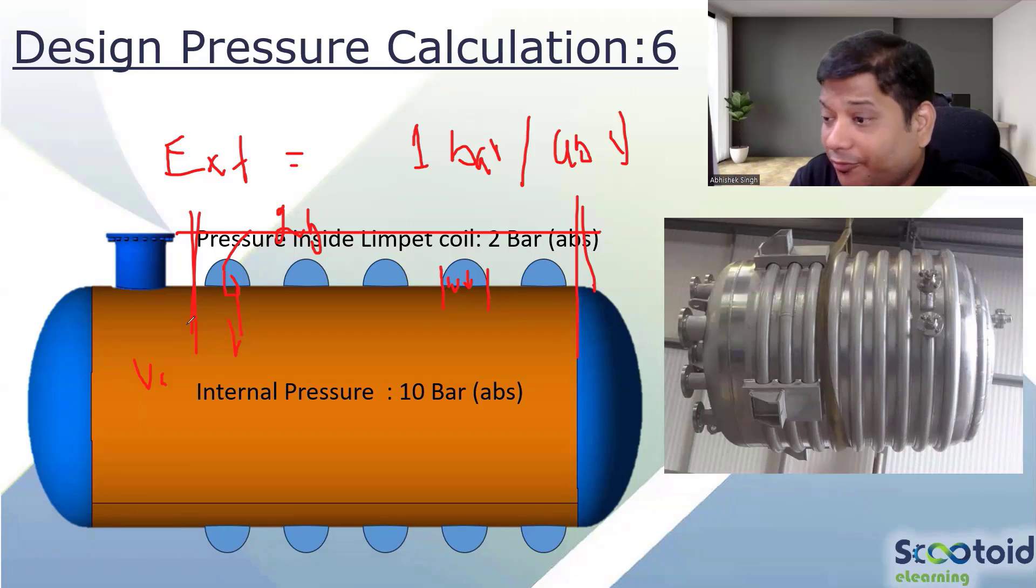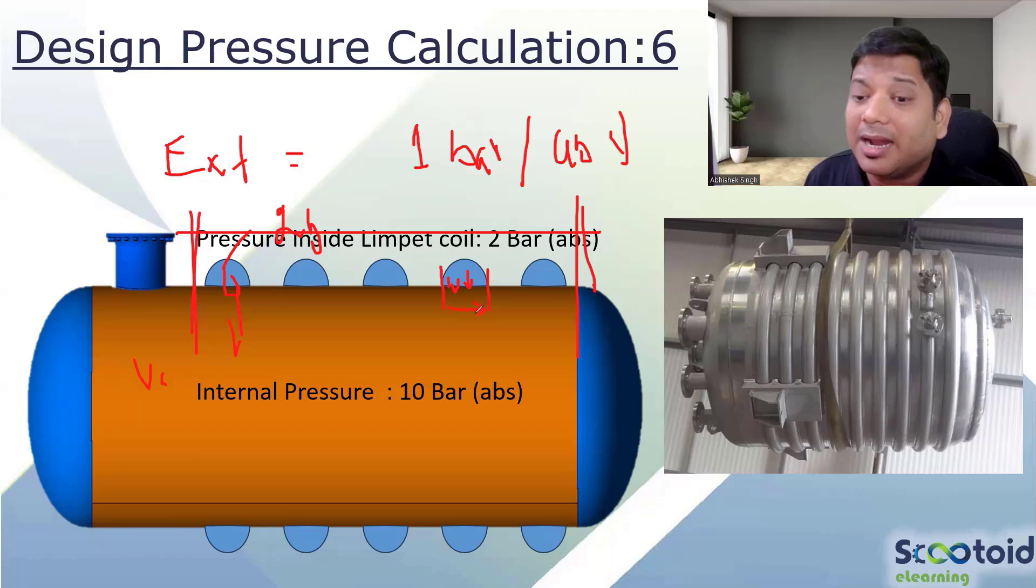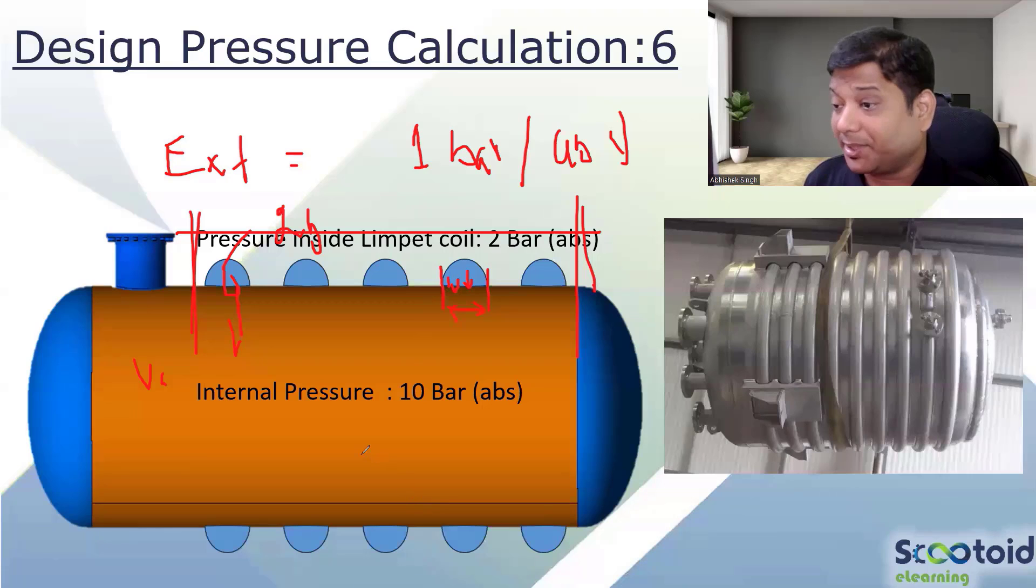That is basically buckling. More length, more problematic. Small length, it is more rigid. So external pressure effect will be much higher if your length is there. In this coil case, because our length is very small, it becomes ineffective. So you don't have to do the external pressure calculation for two bar. If the vacuum exists, one bar is sufficient.